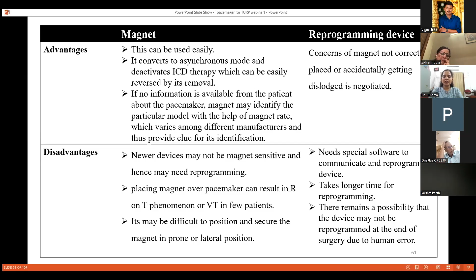Describe the effect of magnet application on pacemaker function. During surgery, as we discussed, there will be electromagnetic interference from the electrocautery. The current from the electrocautery is not restricted to the surgical site. It will pass through the overall body. So this electrical stimulus can be misinterpreted by the pacemaker, and the pacemaker may stop at that time without giving the electrical stimulus. This results in decreased output. To avoid this, we have to convert the pacemaker to a fixed rate asynchronous mode by application of a magnet. The magnet is placed over the pulse generator to trigger the reed switch present in the pulse generator, resulting in a non-sensing asynchronous mode with a fixed pacing rate.